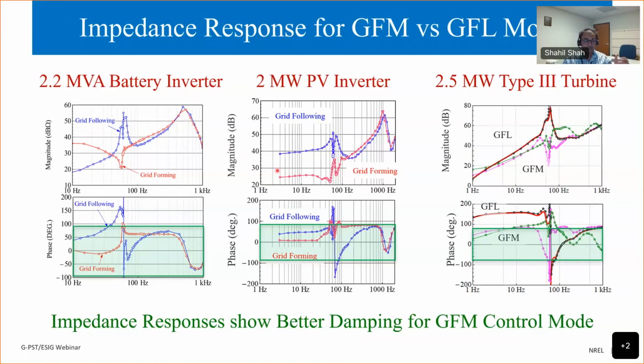Now, I would like you to focus on the magnitude response first. For grid forming mode, the device is trying to act as a voltage source, and we know that an ideal voltage source has zero impedance. So most IBRs, when operated in grid forming mode, will have a lower impedance compared to when they're operated in grid following mode. So we can use those impedances to really define how good a voltage source it is behaving, so define specifications. We can also use it to understand the damping characteristic.